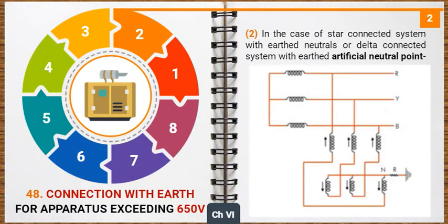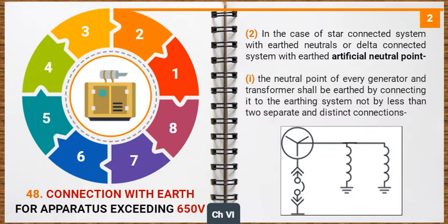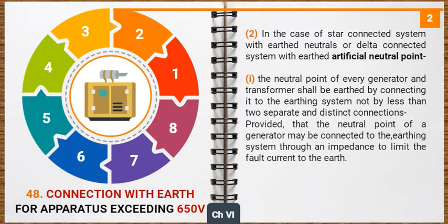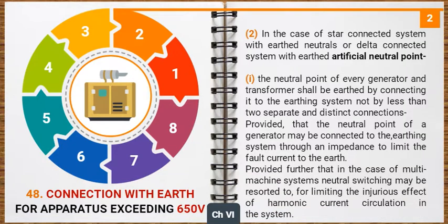In the case of star-connected system with earthed neutrals or delta-connected system with earthed artificial neutral point, the neutral point of every generator and transformer shall be earthed by connecting it to the earthing system, not by less than 2 separate and distinct connections. Provided that the neutral point of a generator may be connected to the earthing system through an impedance to limit the fault current to the earth. Provided further that in the case of multi-machine systems, neutral switching may be resorted to for limiting the injurious effect of harmonic current circulation in the system.